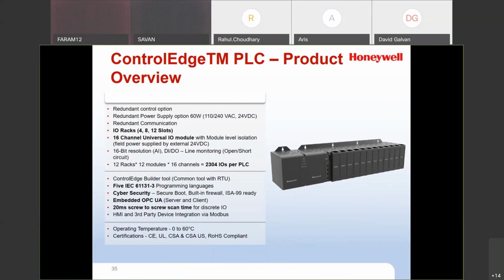You can, via star, via ring, expand that. You can lay out remote IO wherever you need in the plant, and then you can have your CPM either redundant or simplex in your IER, ECR, MCC, server room, wherever you need it to be. Okay, very powerful there. It comes in 2 forms and fashion when it comes to your IO rack and your CPM rack. Your IO rack and your CPM rack can be fully detachable, where you have your CPM rack in a central location, and then you have your I/O rack spread out via that ring or via that star in remote areas.